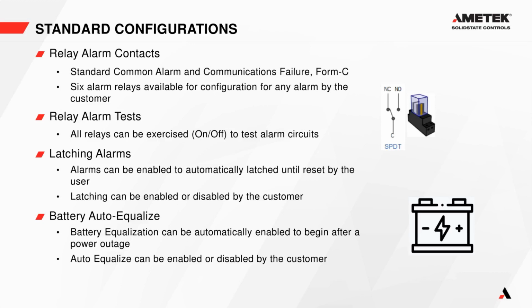We have a user configurable latching alarm option. So when an alarm happens, say you get a low DC voltage because your battery is discharging, but then AC power comes back and your battery is charged back up, that alarm will be latched because it was in the low DC voltage state, but then it exited it. So that will be a latched alarm, which will appear yellow on the screen, and requires the customer to acknowledge that the alarm occurred before the system goes back to its normal operating state. Like I said, this latching alarm can be configured by the customer using the setup screen.